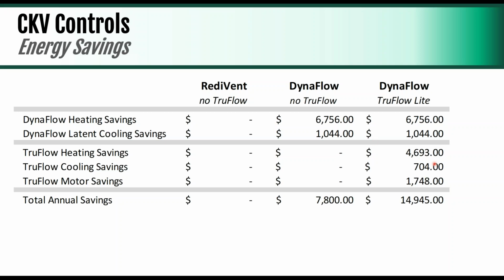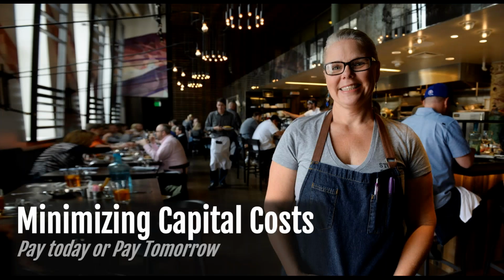So we're going through and we can modify that. But as you can see, just based on having high efficiency hoods, you're at about $8,000 annual savings. By adding the demand control, you're moving up to about $15,000 annually. So it's a pretty significant investment, and where we really see that adding up is looking at capital costs.